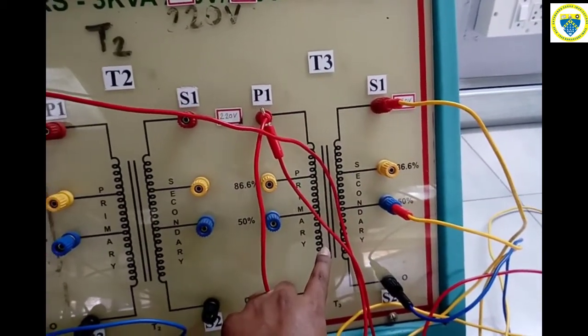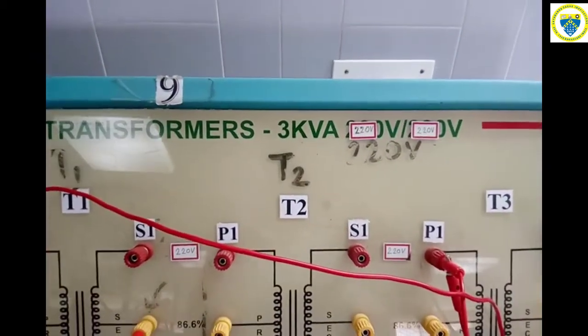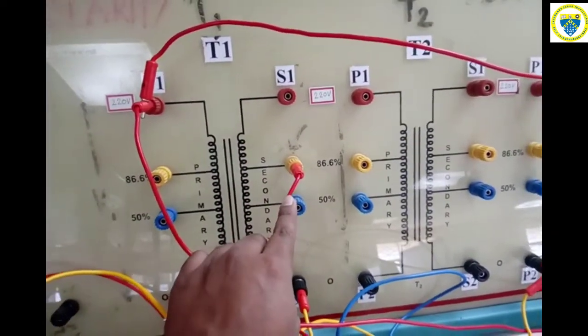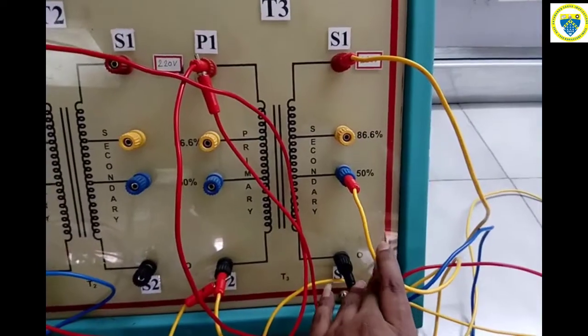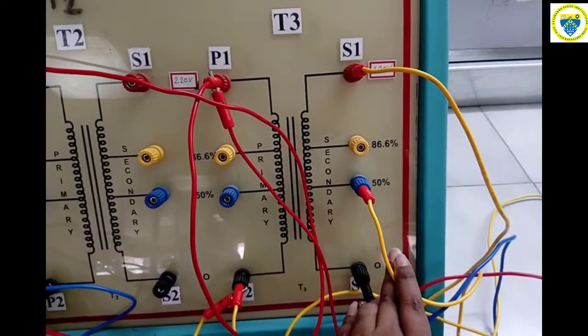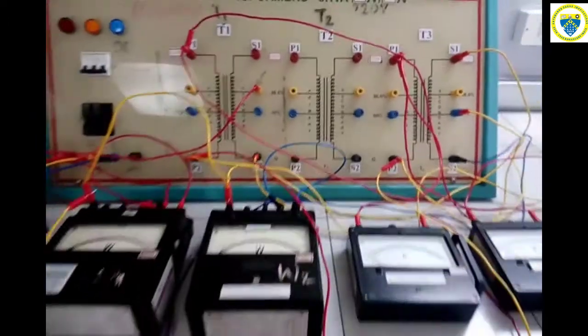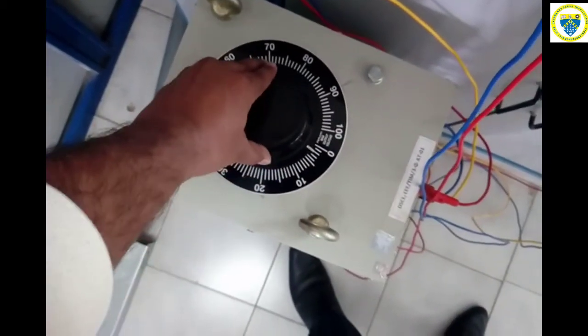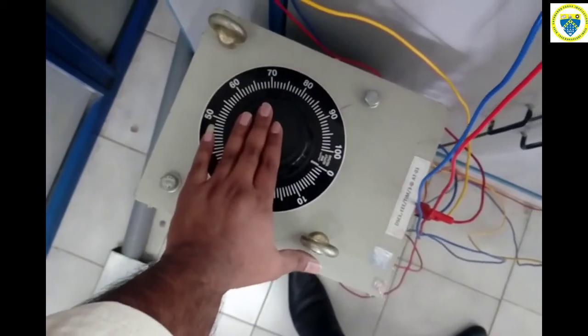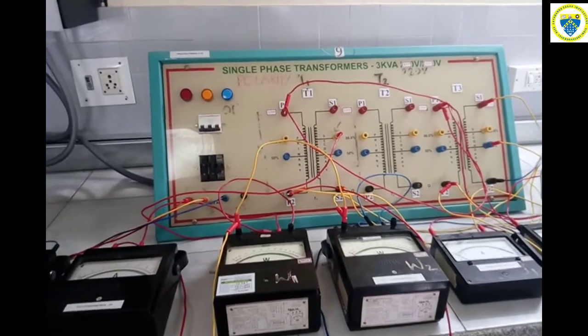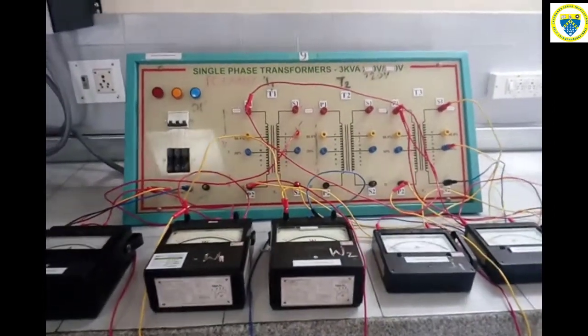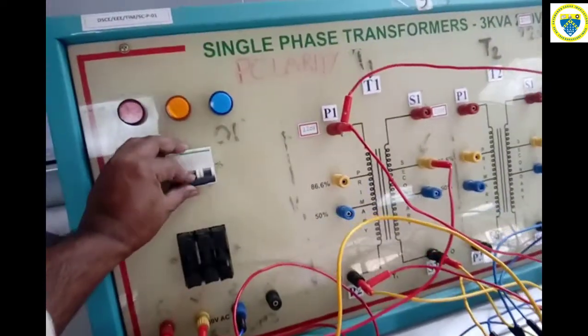Main transformer T1 and the teaser transformer T2. Both the transformers have a rating of 3 kVA and 220 volt. So here at the secondary of T1 we have used 86.6% tapping, and at the teaser transformer, we will have 50% tapping. So before starting the procedure, we should confirm that the 3-phase auto transformer is kept at 0 position. If not, we should bring the 3-phase auto transformer to 0, and then switch on the 3-phase supply. After confirming the 0 position, we can switch on the 3-phase supply.